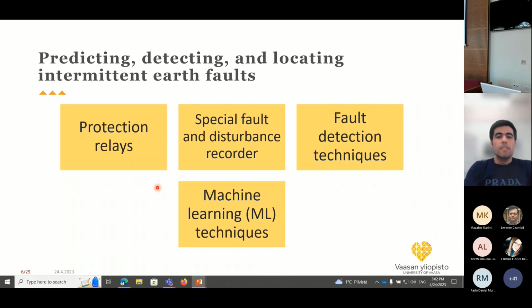Since we started this study recently, about 3 months ago, we did a literature review, and some works proposed using protection relays. But since they use a lower sampling rate, they are incapable of predicting such earth faults. However, in rare cases we have a sinusoidal intermittent earth fault, and just in this case, relays are effective.